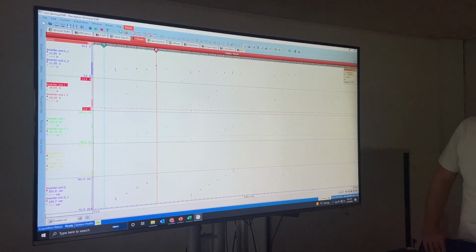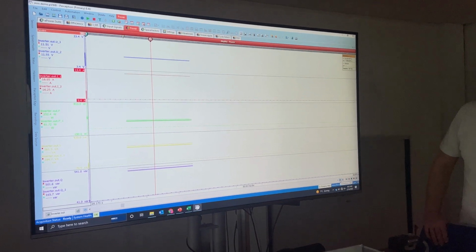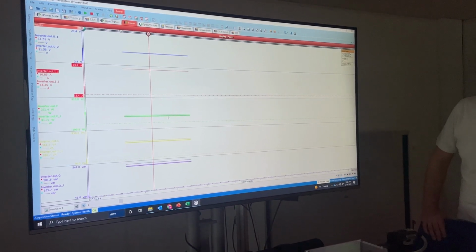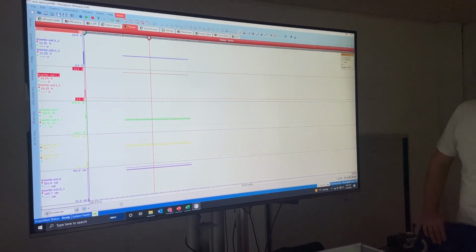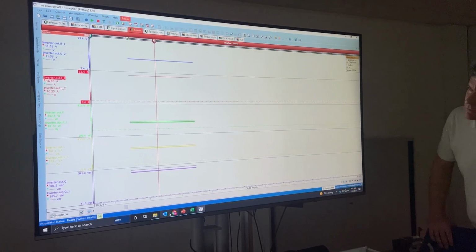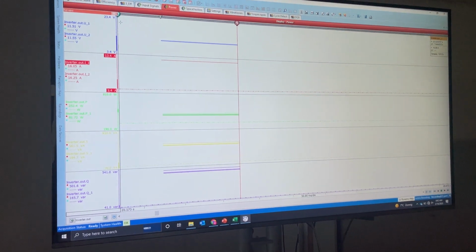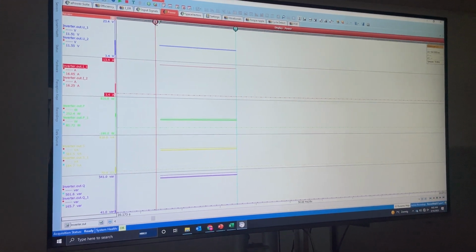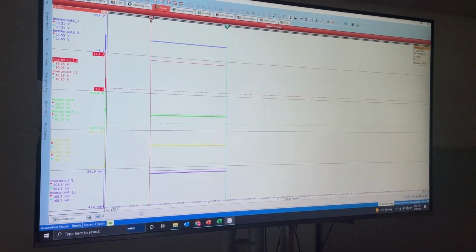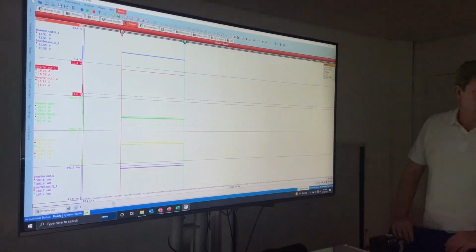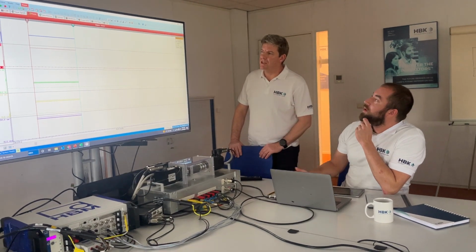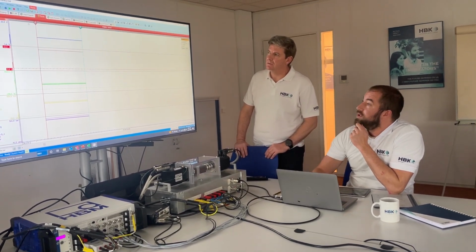I can go to my power and I can look at a point. These are all the points, right? These are all of those trigger points. Okay. And I see a super stable power measurement, super stable RMS, and if we look, it's 50 milliseconds per division. Okay. Each one of these points is 0.1 seconds. Because of the cycle tick, add a point, measuring, add a point, measuring, add a point, measuring. So you can move through this quickly. 10 times a second. Yeah, 10 times a second.